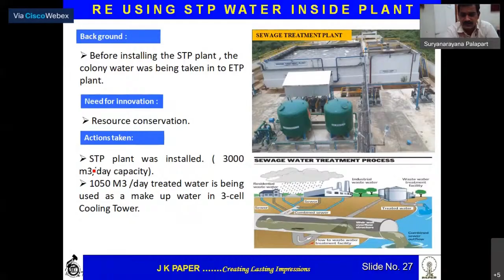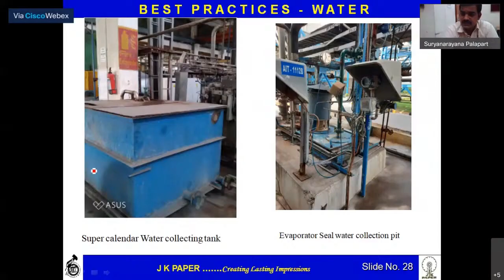For the evaporator seal water collection pit, we collect the seal water from the evaporator plant in a pit, with 2 conductivity meters installed, and pump it back to the cooling tower as makeup. The point is that water saves power through pumping energy, but in several instances water has also saved us steam.